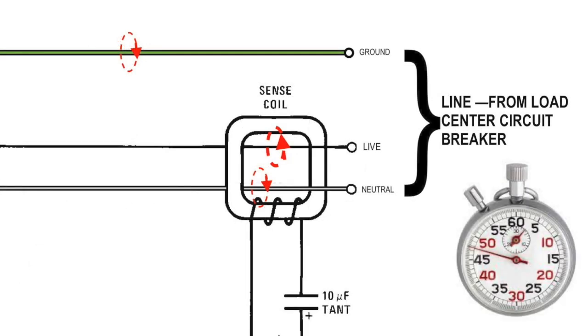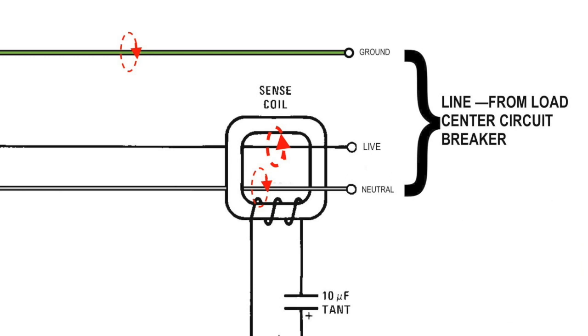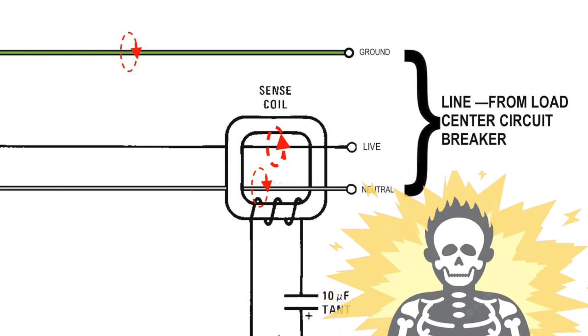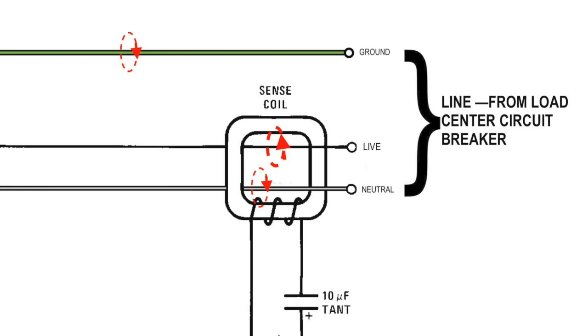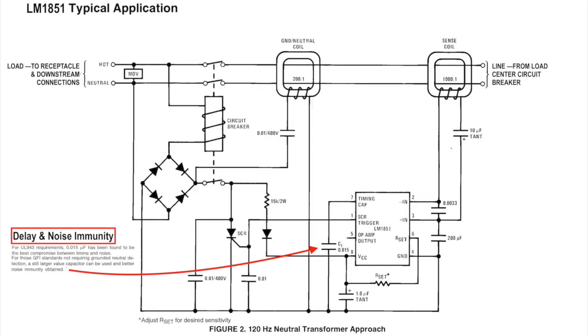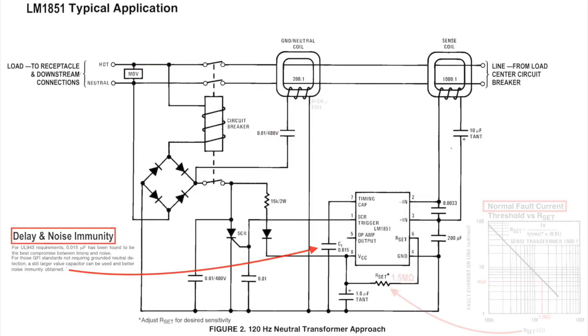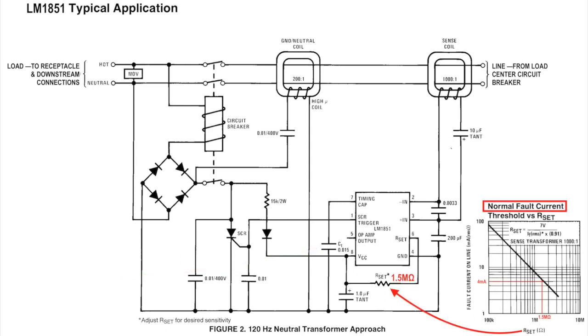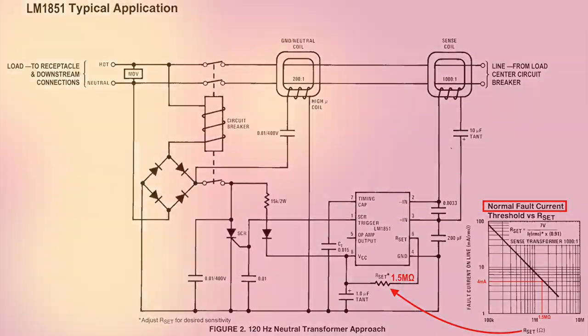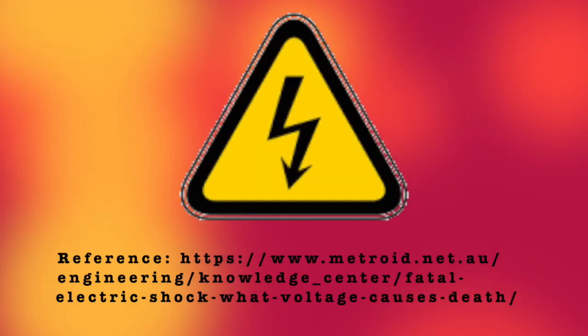There is a time delay between when the fault condition is detected and when the switch is opened. This reduces the chance that the switch is falsely tripped, but can also permit the fault condition to go on longer, especially if there isn't much current flowing on the ground. The time delay and sensitivity values are set by external components and can be customized for different applications. Unfortunately, it doesn't take much current to kill you. As little as 7 milliamps across the heart for 3 seconds can kill.